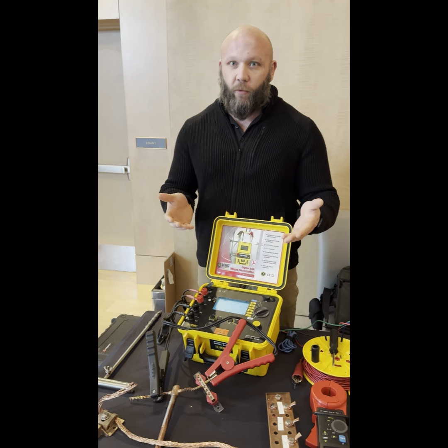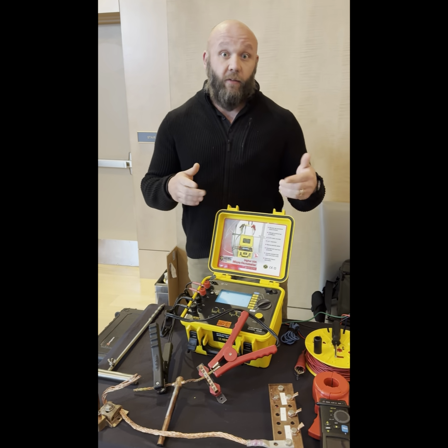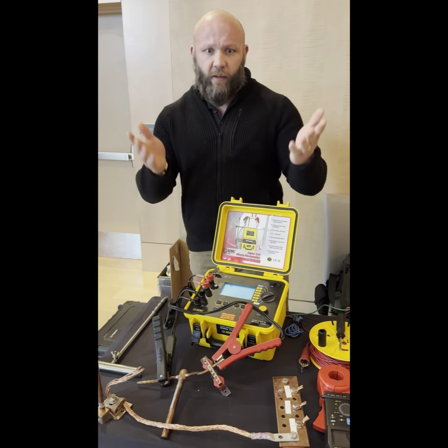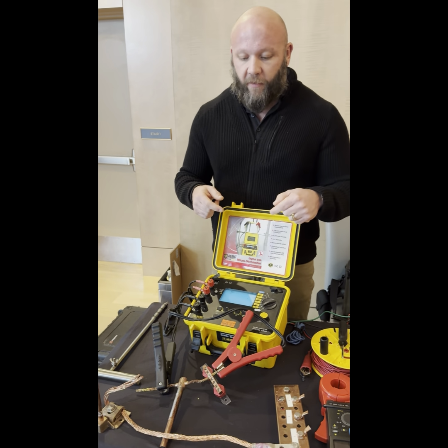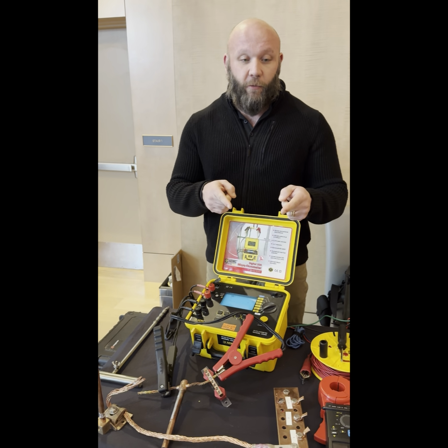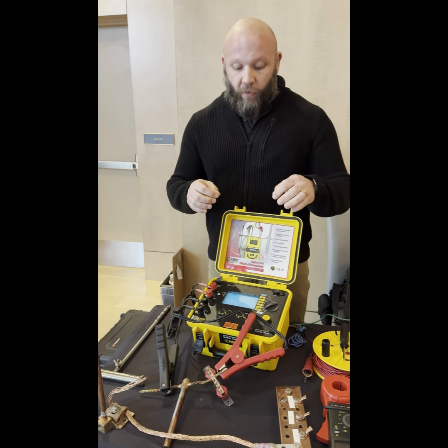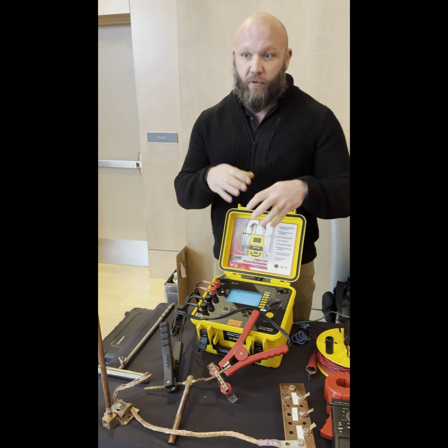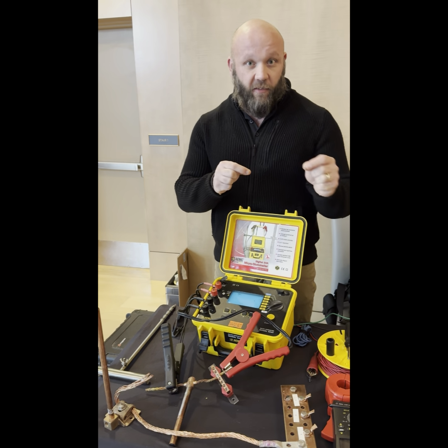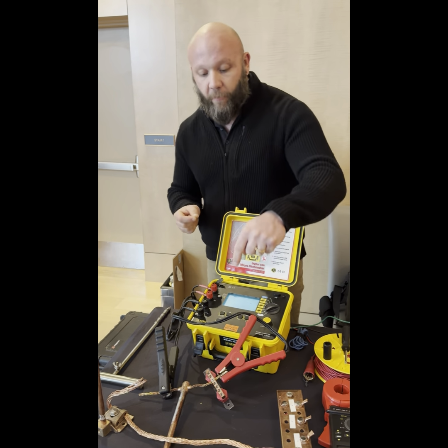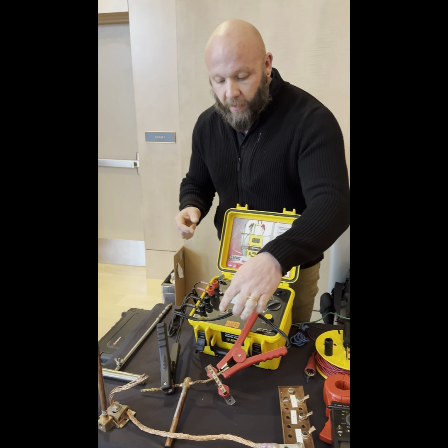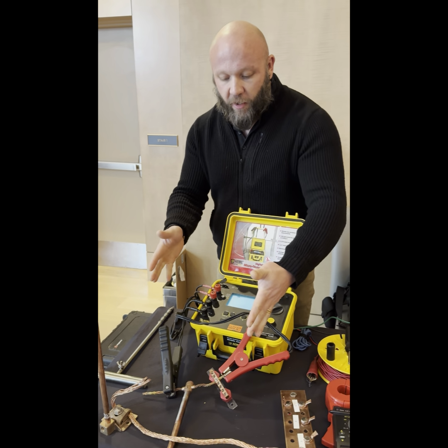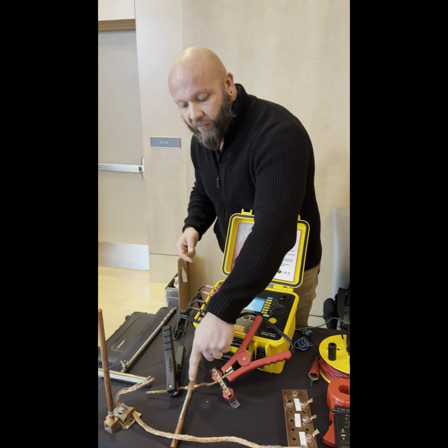Let's talk about controlling variables in testing. And this could apply to anything that you do, but specifically with testing, you are always the biggest reason that things are inaccurate. So here, just as a quick example, I have a micro-ohmmeter capable of measuring incredibly low amounts of resistance in the micro ohms. And I've set my leads up to be kind of far away from each other, and I want to measure the resistance of this bond.